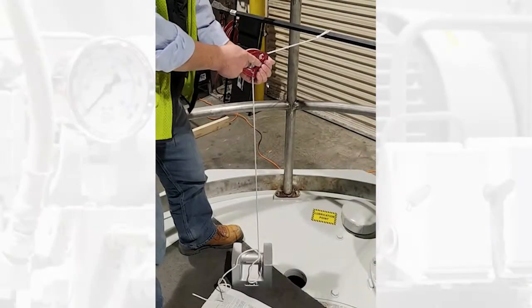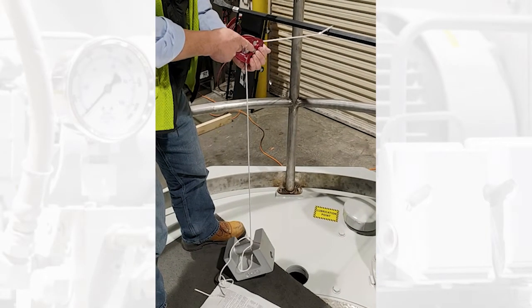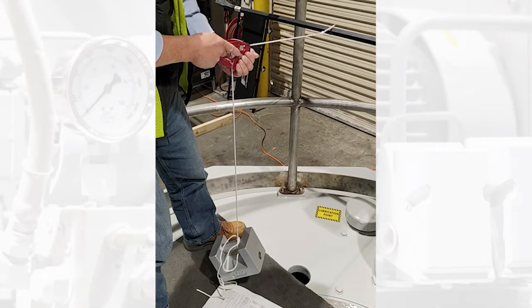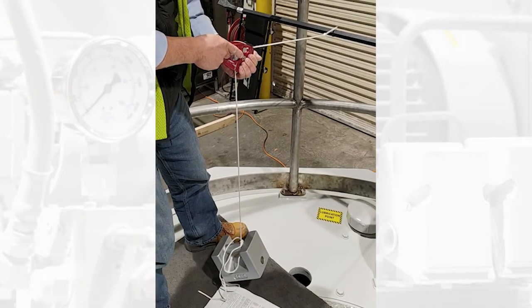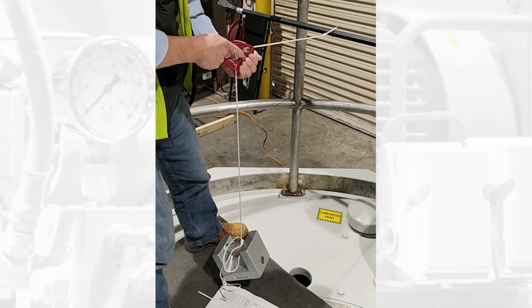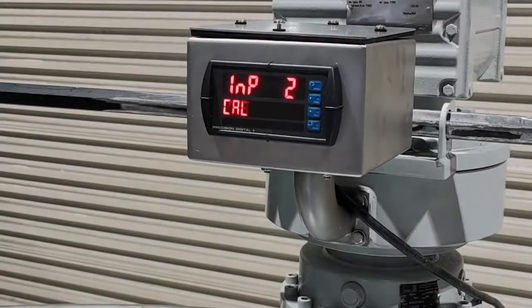Pull the pulley toward yourself, lifting the weight slightly off the floor. The weight does not have to be held very high, just enough to ensure that the entire weight is being supported by the rope alone. Hold that position as stable as possible for the next few steps of the calibration. While you are holding the pulley and weight constant, have a second person press the buttons on the torque display for you.